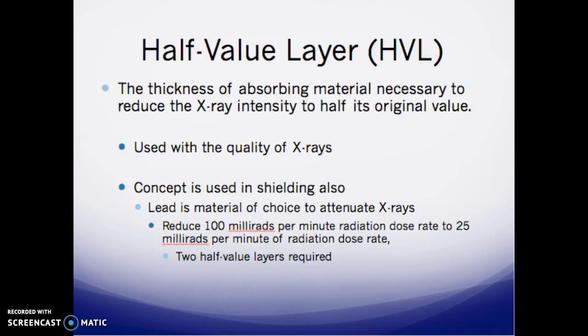The half value layer requires 3 millimeters of aluminum equivalent — it's the thickness of absorbing material necessary to reduce x-ray intensity to half its original value, used to assess x-ray quality. For shielding, lead is the material of choice. Example: to reduce a 100 mrad/min dose rate to 25 mrad/min, you need two half value layers — first halving 100 to 50 mrad/min, then halving again to 25 mrad/min.